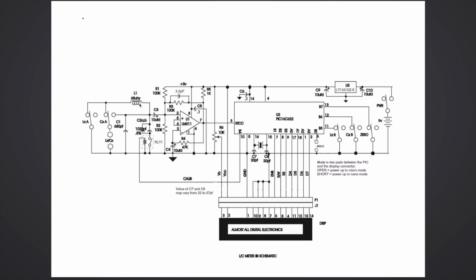When it starts up, it's just got L1 and C1 in parallel. You can measure the frequency those oscillate at. Then it's got a precision capacitor here you can switch in to do the calibration. It'll store those values.